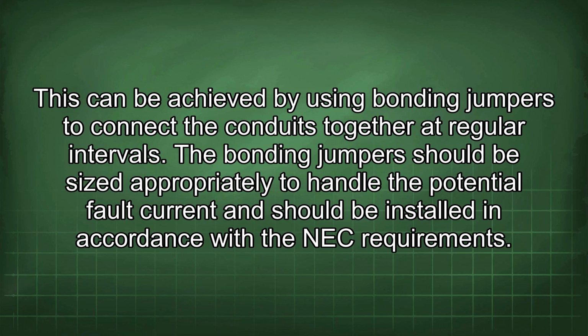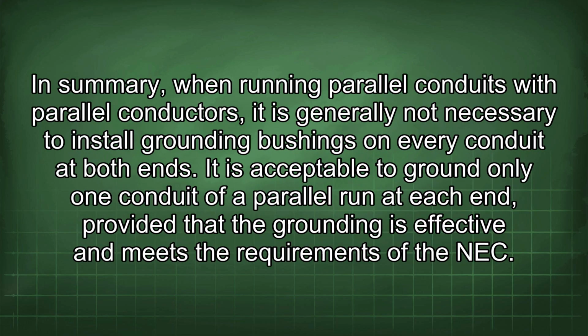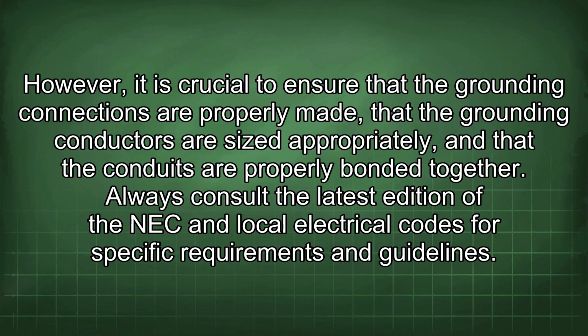the NEC requirements. In summary, when running parallel conduits with parallel conductors, it is generally not necessary to install grounding bushings on every conduit at both ends. It is acceptable to ground only one conduit of a parallel run at each end, provided that the grounding is effective and meets the requirements of the NEC. However, it is crucial to ensure that the grounding connections are properly made, that the grounding conductors are sized appropriately, and that the conduits are properly bonded together.